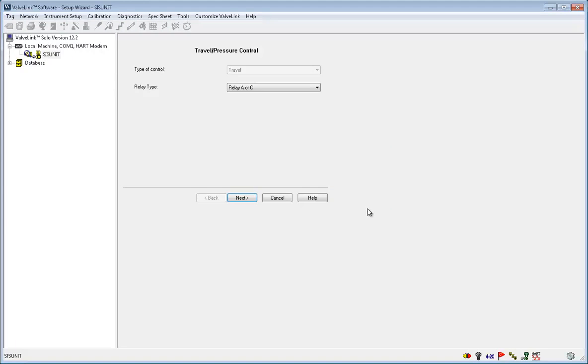Since it is an SIS device, you can only have travel control, but this first window asks you to choose the relay type. You can choose the best type of relay for your device, but the one I am working with is a Relay C. So choose your relay type and click Next. Now enter in your maximum supply pressure and your pressure units of preference. I'm going to leave the units in PSI and leave my max pressure at 90 PSI. Click Next to move on.